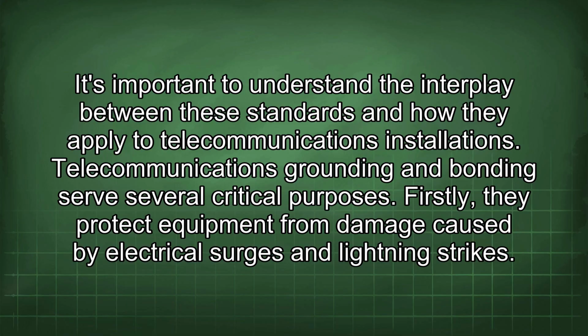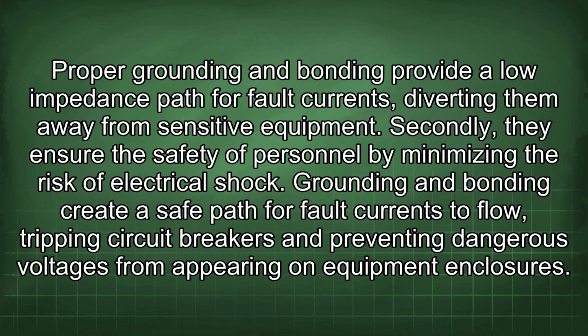Telecommunications grounding and bonding serve several critical purposes. Firstly, they protect equipment from damage caused by electrical surges and lightning strikes. Proper grounding and bonding provide a low impedance path for fault currents, diverting them away from sensitive equipment. Secondly, they ensure the safety of personnel by minimizing the risk of electrical shock.